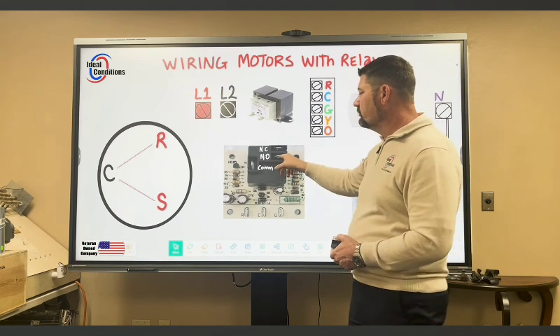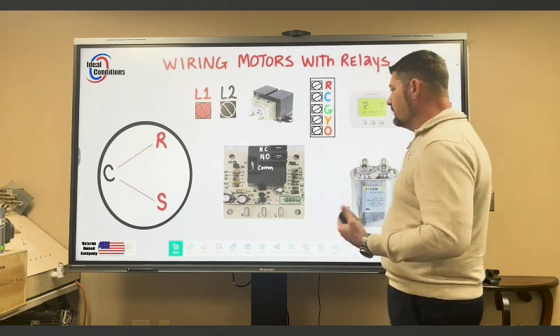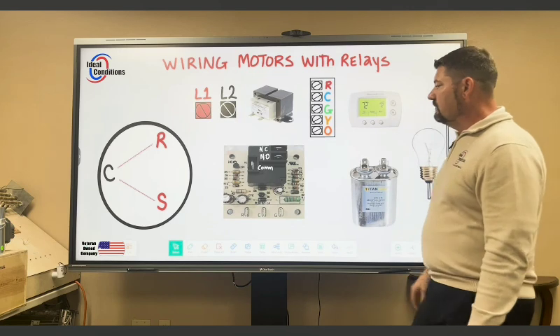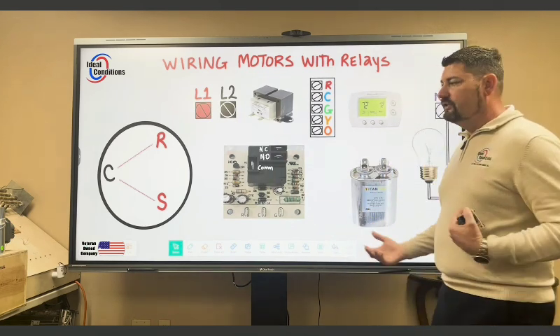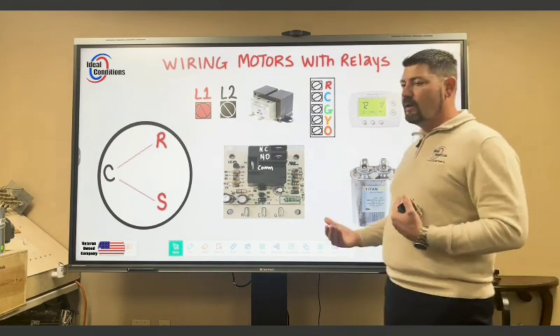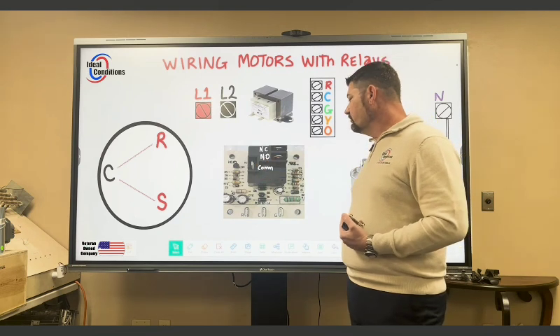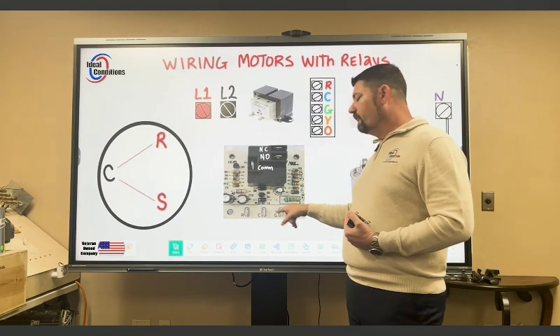Typically, you're going to wire your motors to your normally open. However, earlier in the video, we wired the normally closed portion to a light bulb just to show you that there's always power present between common and normally closed when there is no call for G.